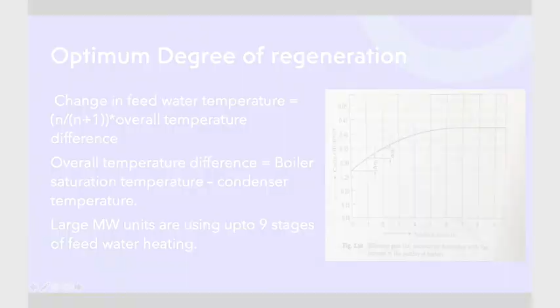It is impossible to do 100% Carnotization of the Rankine cycle, because for that we have to install an infinite number of heaters, and that solution is practically not feasible. So the next thing which comes to our mind is what would be the optimum degree of regeneration. One thing to note here is that normally the maximum number of heaters which have been installed in any particular unit is 9. After that, it has been seen that if you add a further heater, though you get an improvement in efficiency, that improvement doesn't justify the cost. That's why the maximum number of heaters installed in any system has been limited to 9.